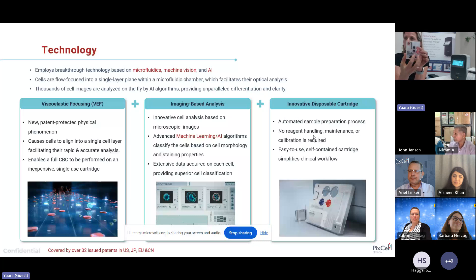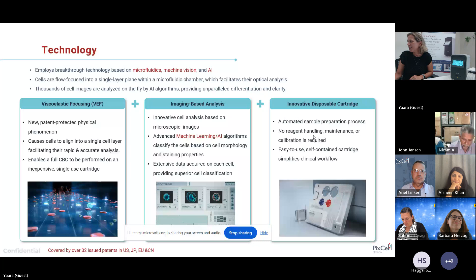And the cells, after mixing with the reagents, flow into a microchannel where the cells are focused and the reader counts the cells. So from the user's perspective, the cartridge-based solution is very simple, like an espresso machine, okay? The sample processing is done automatically, and there is no need for bulk reagents, no need for cleaning or maintenance, and no calibration is required, which is, of course, very, very important for a point-of-care device.